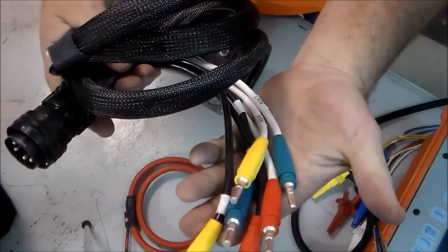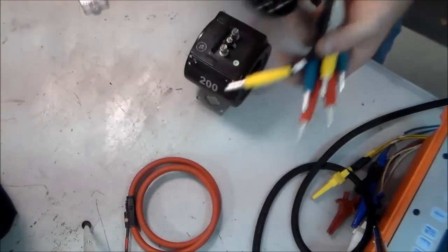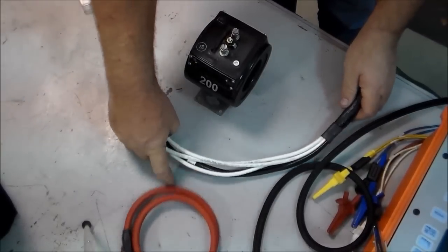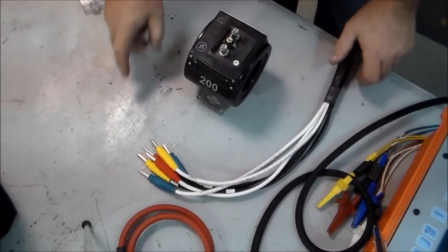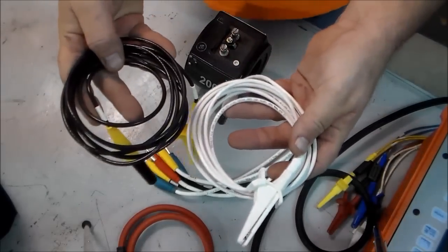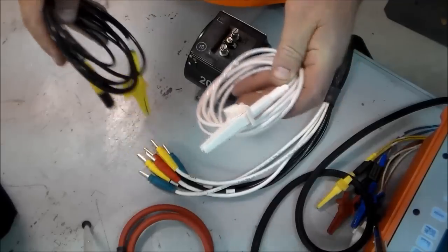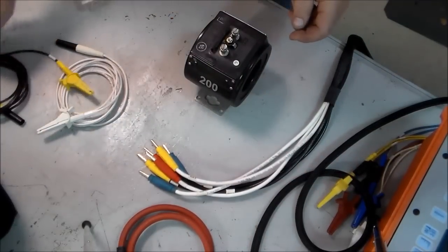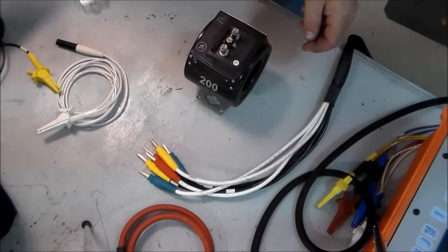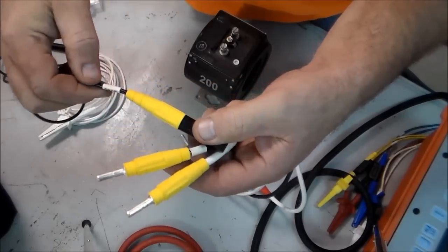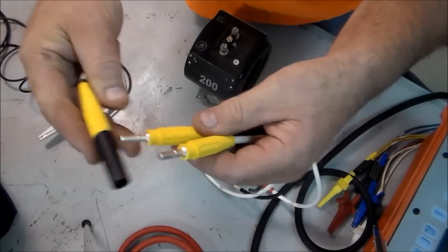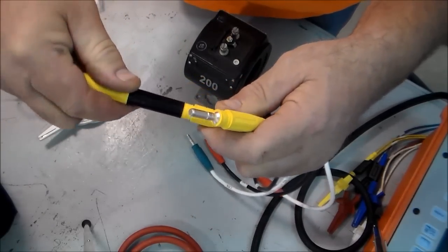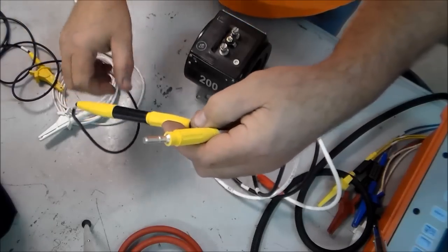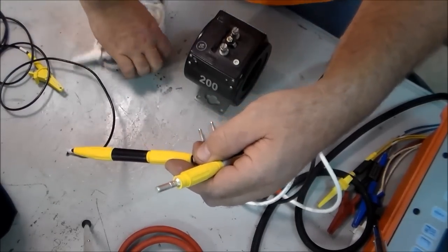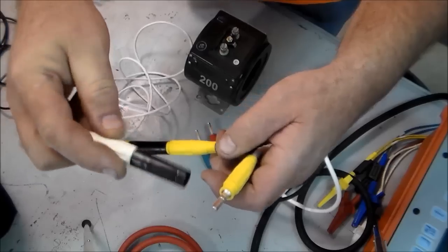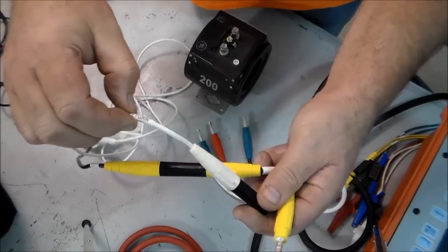Next up, let's get the 50 amp multi-pin current cable out. And then your two direct current cables. The Powermaster uses the B-phase current leads to measure the secondary output of the CT. And in just a minute, we'll use the red current leads to drive the primary. And we'll just be sure we match our plugs, drive and return.